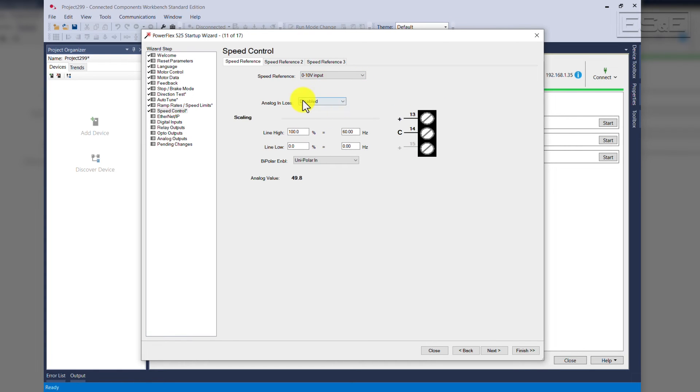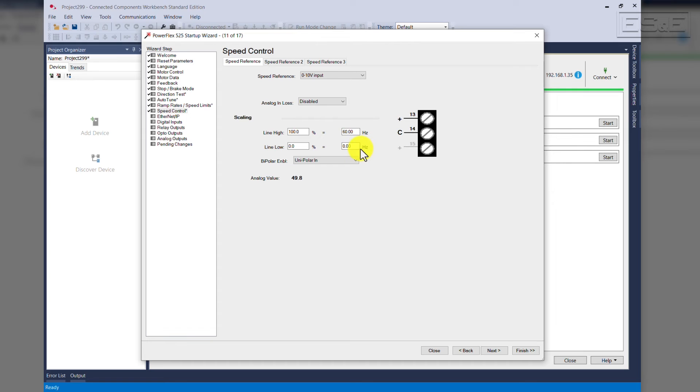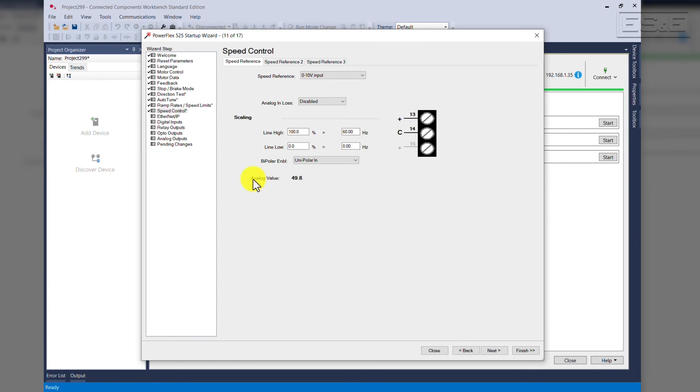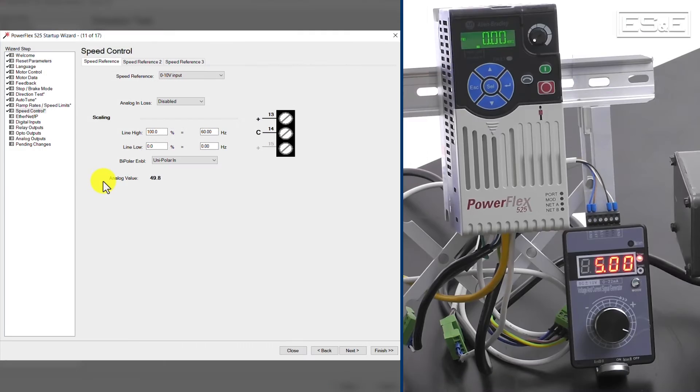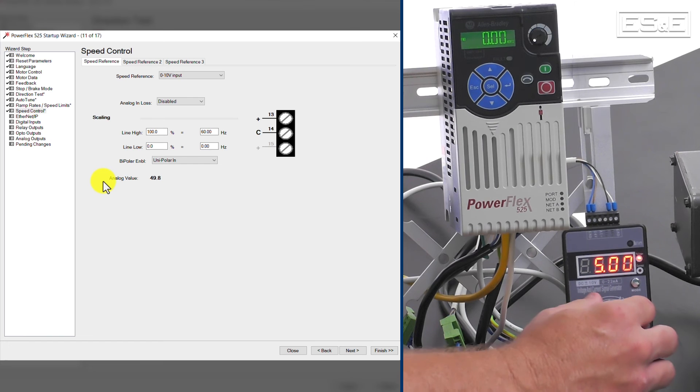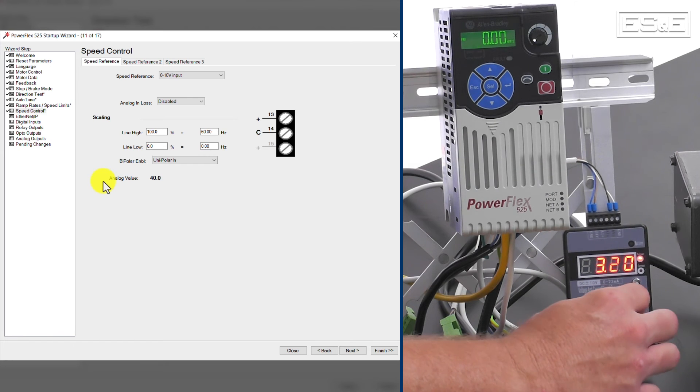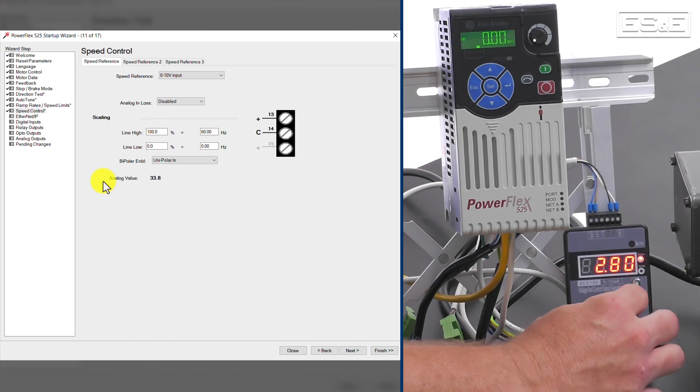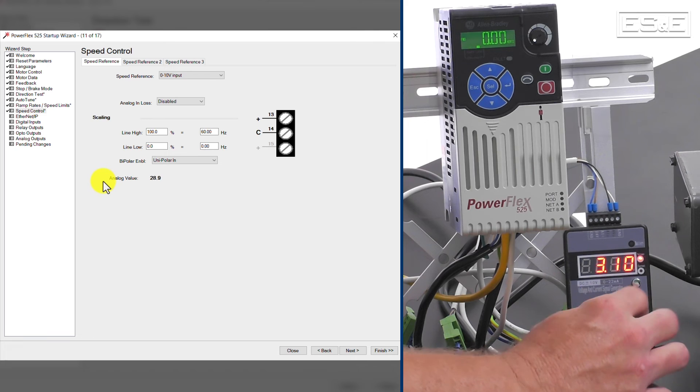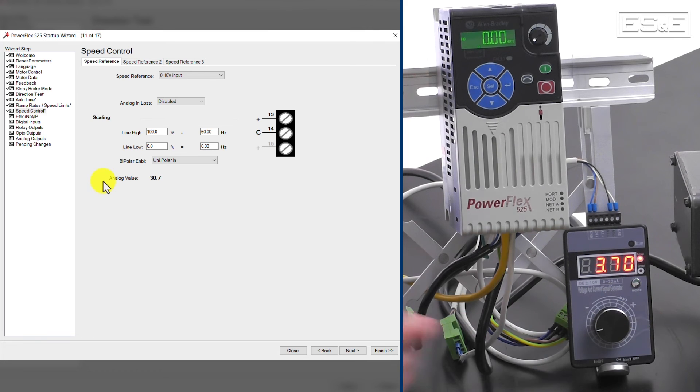As you can see the scaling here, zero to ten, so zero to 100 percent, or zero to ten volts, we've actually got zero to 60 hertz. That is how we scale. Also at this point, you can look at the analog value. You can actually change it. As I'm changing, you can see it on the screen. So it's a good point to test your analog voltage.